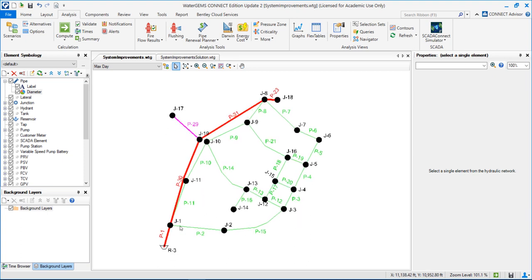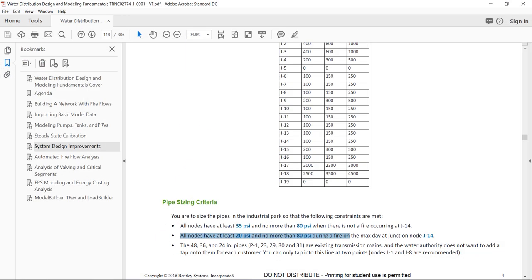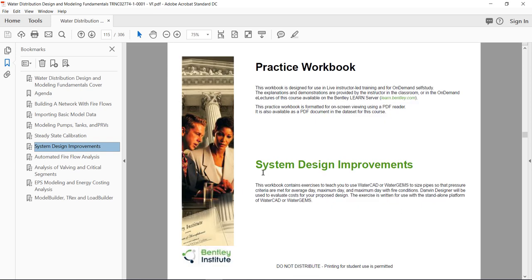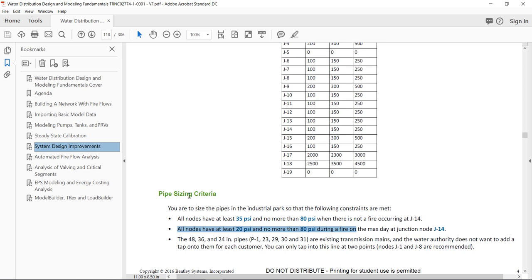The goal is to size and up-size all these green pipes that supply an industrial area. We have three main criteria to meet. If you go to the PDF guide to the system design improvements workshop, you can see the size criteria. First criteria: all nodes should have at least 35 psi and no more than 80 psi when there is not a fire. We should try to meet 35 psi for maximum day demands and verify we have no more than 80 psi when we have low demands.